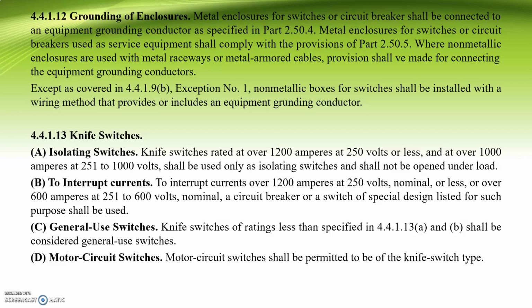Chapter 4.1.13, knife switches. So first is the isolating switches. Knife switches rated at over 1200 amperes at 250 volts or less, and at over 1000 amperes at 251 to 1000 volts shall be used only as isolating switches and shall not be opened under load. So B, to interrupt currents. To interrupt currents over 1200 amperes at 250 volts nominal or less, or over 600 amperes at 251 to 600 volts nominal, a circuit breaker or a switch of special design listed for such purpose shall be used.